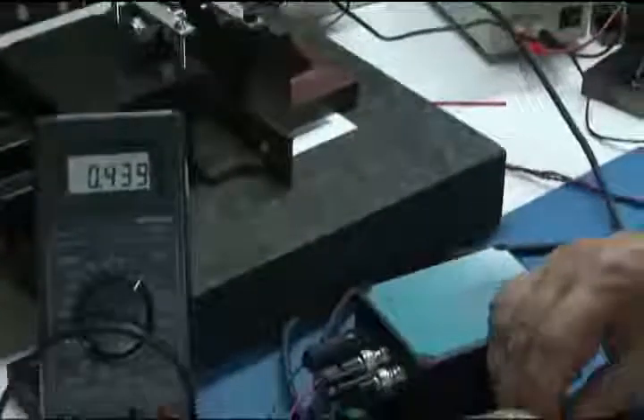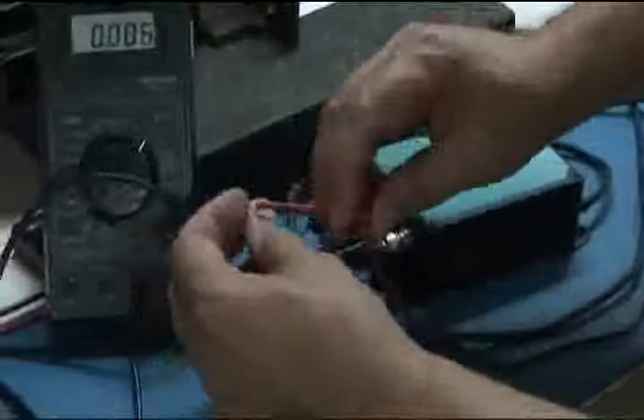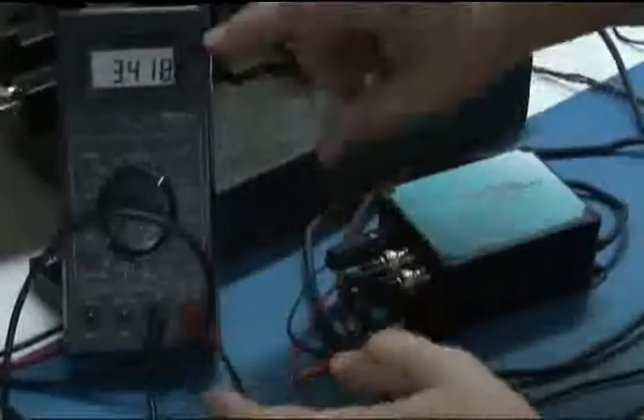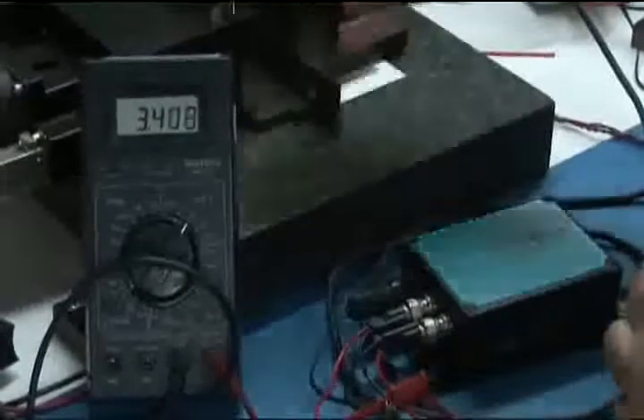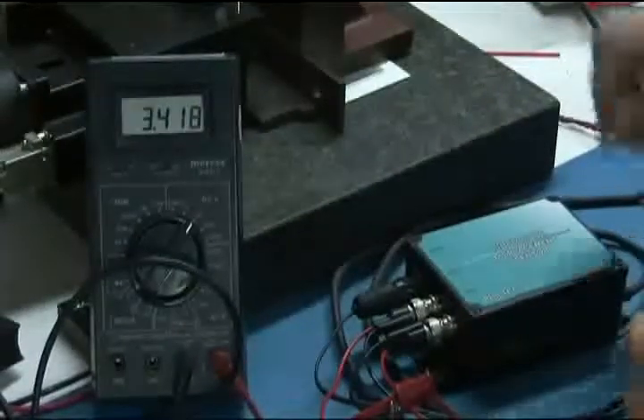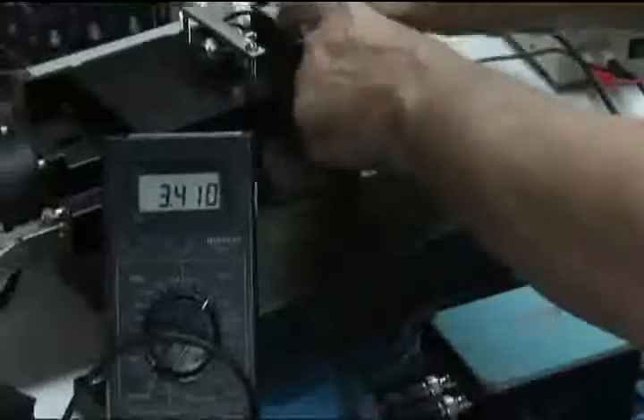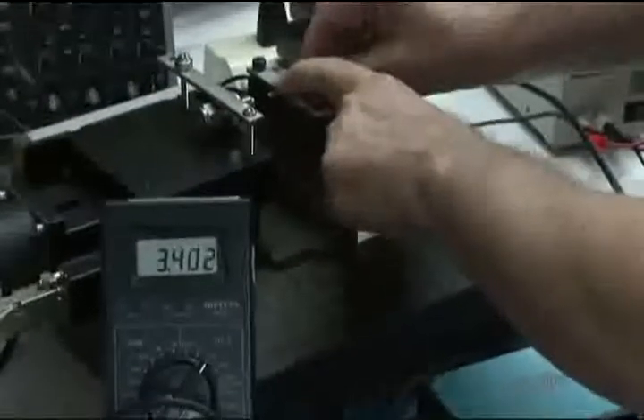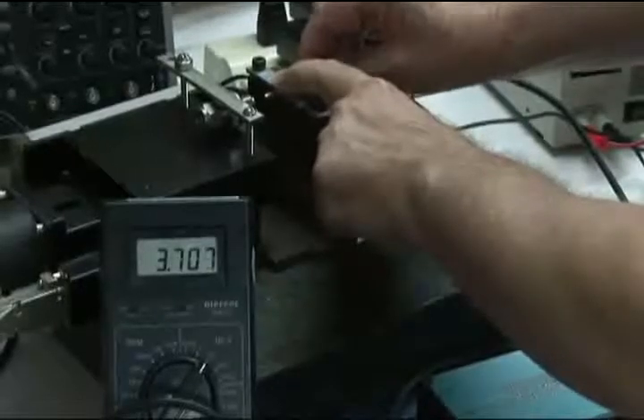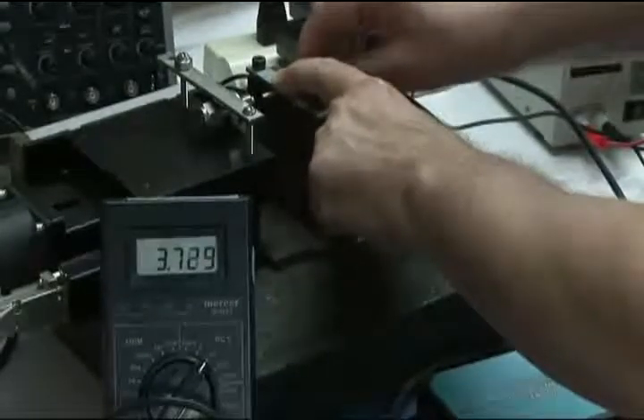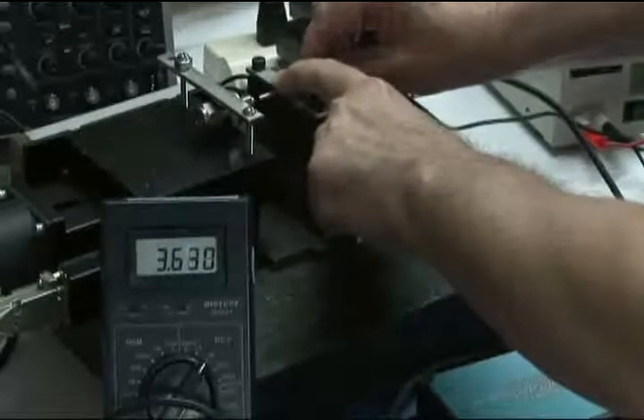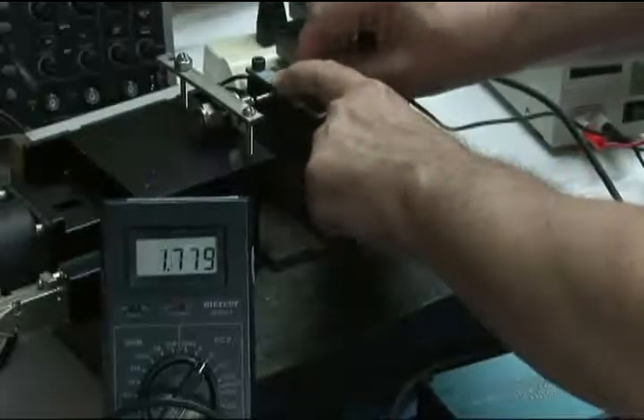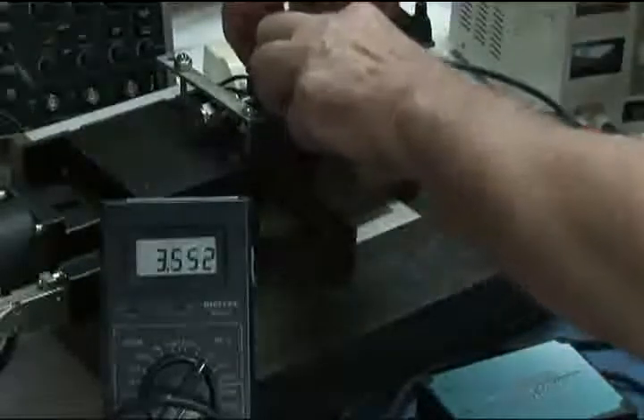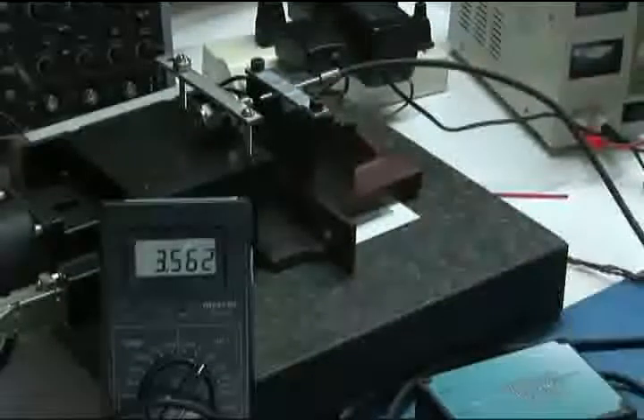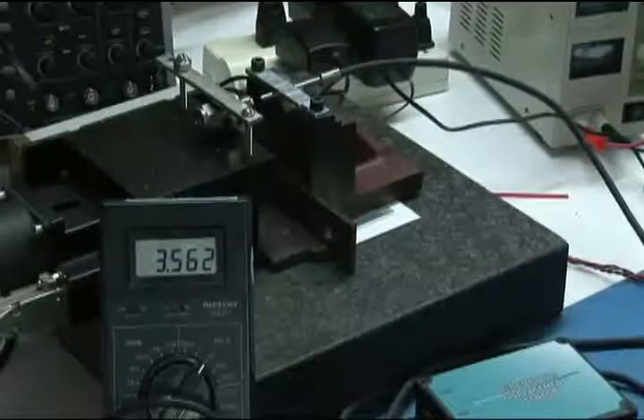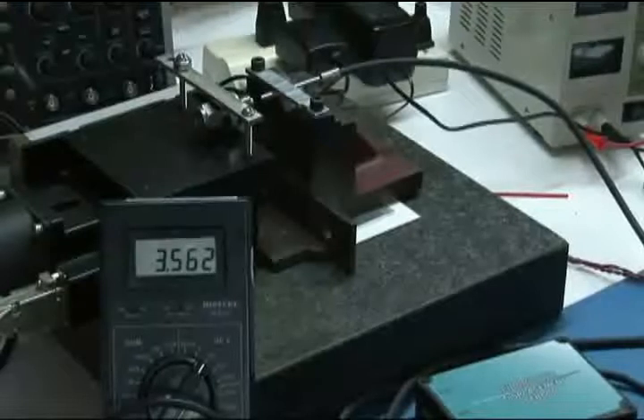Let me show you for the sensor we have here. I'll hook up the voltmeter to the SNR output. And you can see right now, with the output sitting at 5 volts, the SNR is at 3.4 volts, which is a nice value. Now I'm going to slide the probe in, close the gap, and as I close the gap, the SNR voltage peaks out around 3.76, and as I get closer to the sensor, it just goes lower. So we've set these SNR voltages so that they peak out somewhere between 3.5 and 4 volts, which is a nice safe value for good operation.